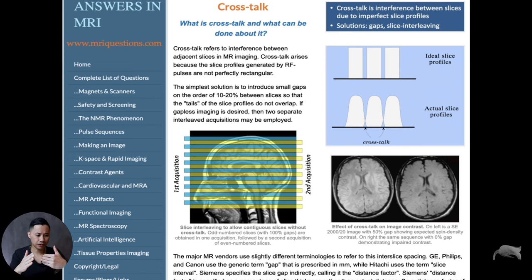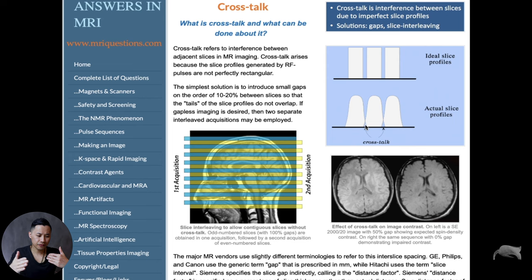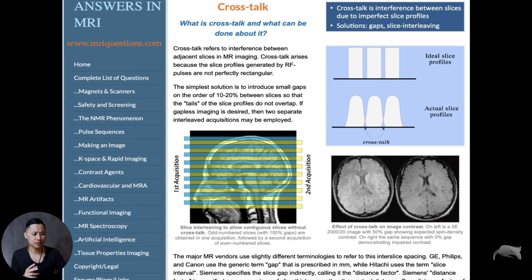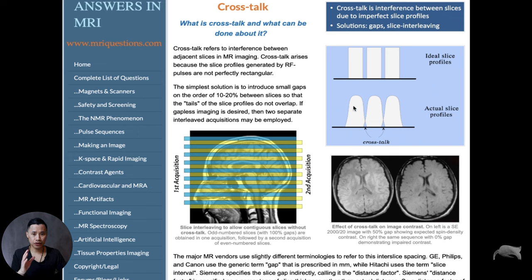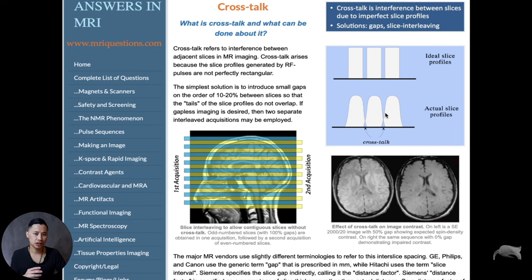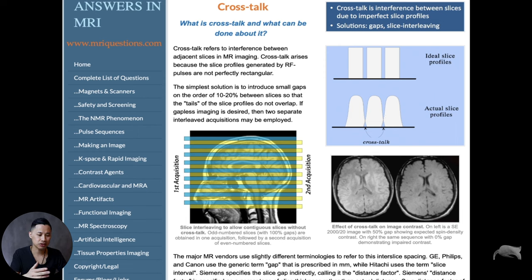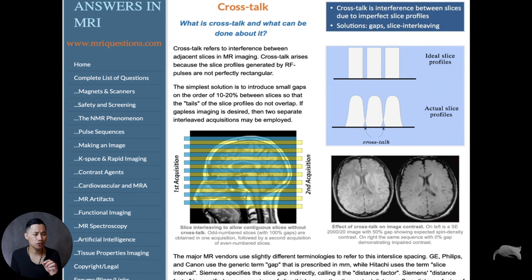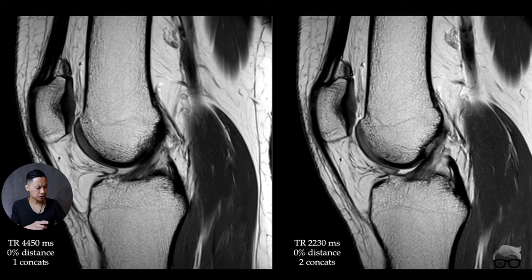Or if you have two concatenations, that means that you are now sampling with the first concat. You're sampling, let's say, slice two, slice four, six. You're jumping in between because the second concat will then sample what's in between. So that the tail won't touch each other and you won't get this artifact. So that's why concats, if you're using zero distance, at least have two or three concats if you're not doing this.